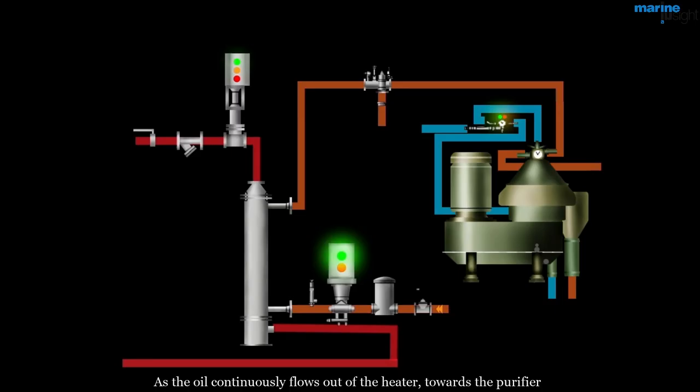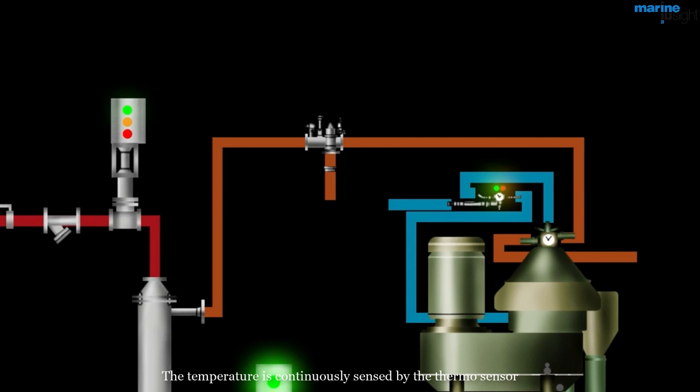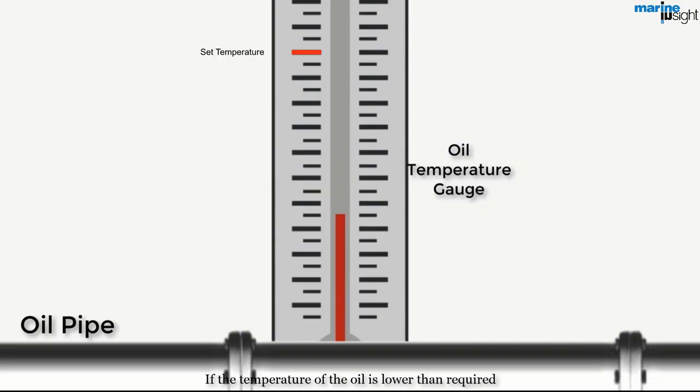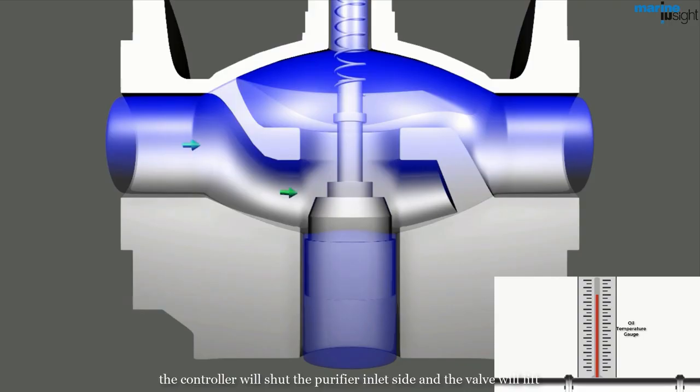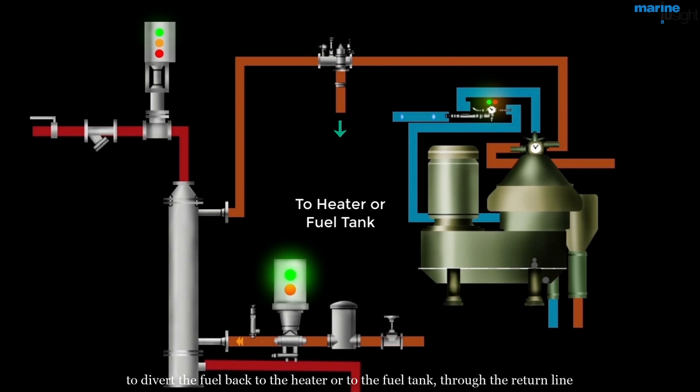As the oil continuously flows out of the heater towards the purifier, it is passed through a 3-way direction control valve, in which temperature and pressure of the oil is monitored. The temperature is continuously sensed by the thermosensor fitted on top of the 3-way valve. The output from the sensor is sent to the main control unit, which will operate the 3-way control valve. The valve can be either pneumatically or electrically operated. If the temperature of the oil is lower than required, the controller will shut the purifier inlet side, and the valve will lift to divert the fuel back to the heater or to the fuel tank through the return line.